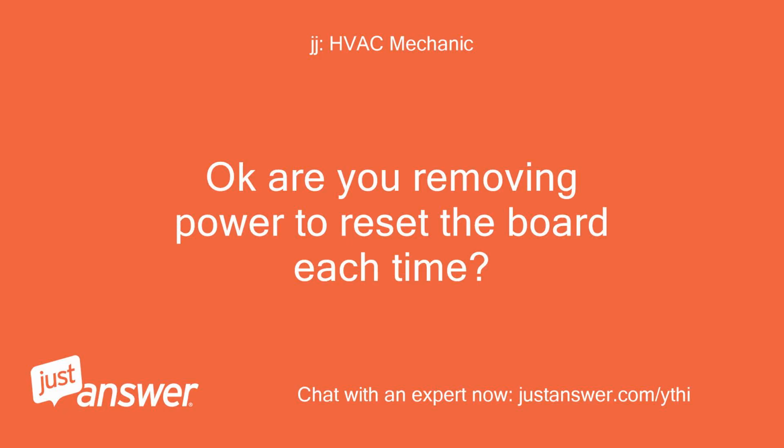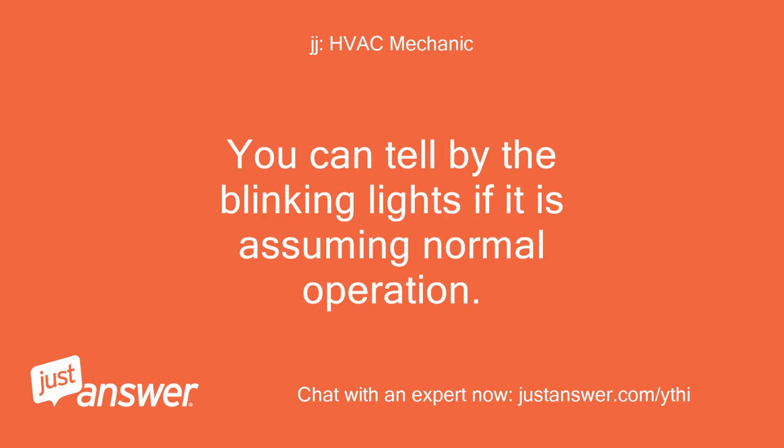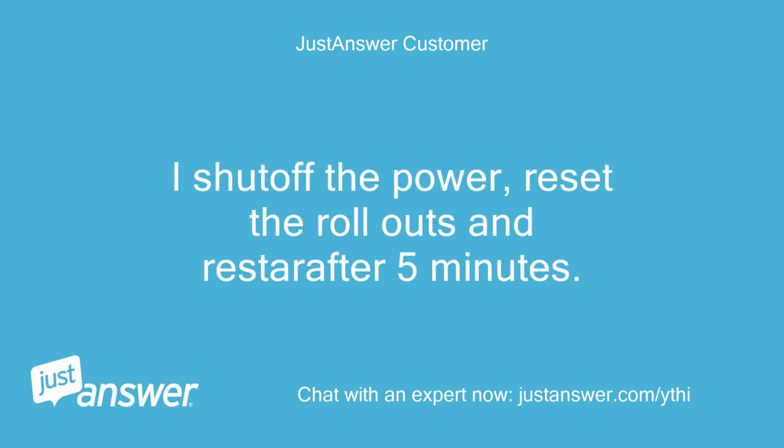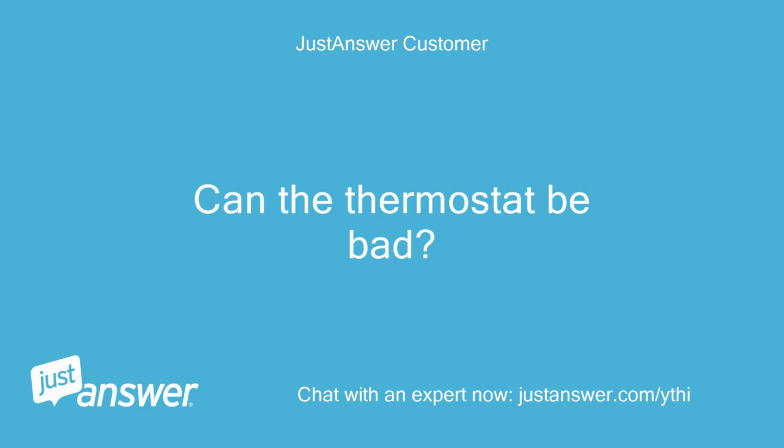Okay, are you removing power to reset the board each time? It may require this reset as well as pressing the manual reset. You can tell by the blinking lights if it is assuming normal operation. One thing that doesn't make sense is how can the ROLLOUT switches trip if the igniter is not allowing ignition? I shut off the power, reset the ROLLOUTs and restart after 5 minutes. Keep getting 6 flashes. Can the thermostat be bad?